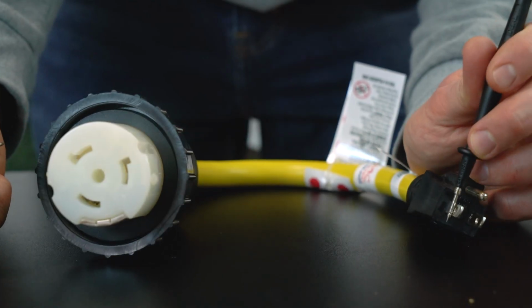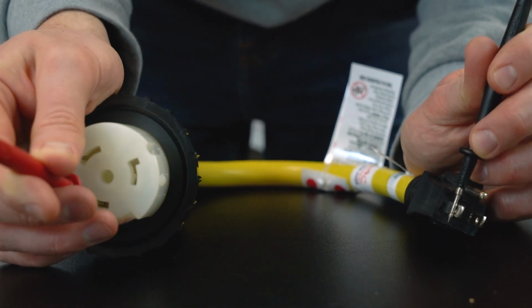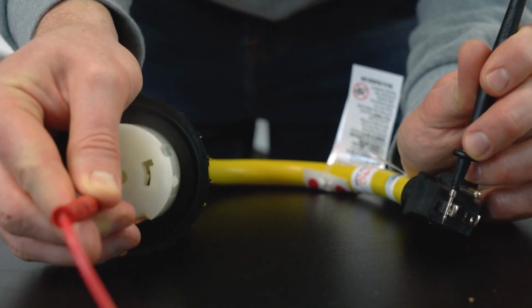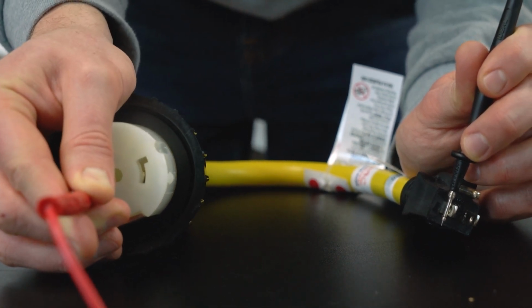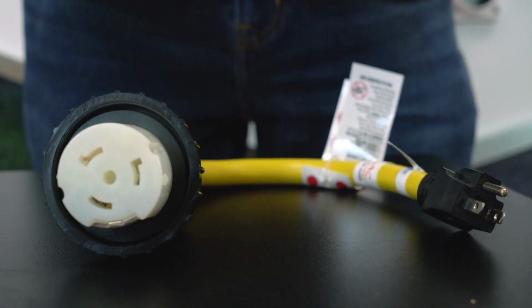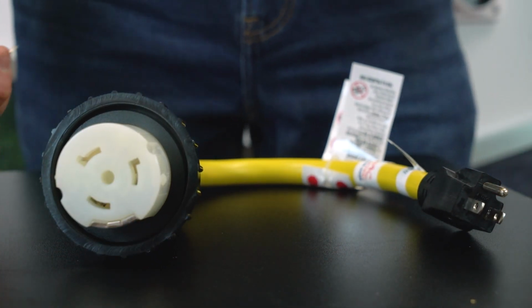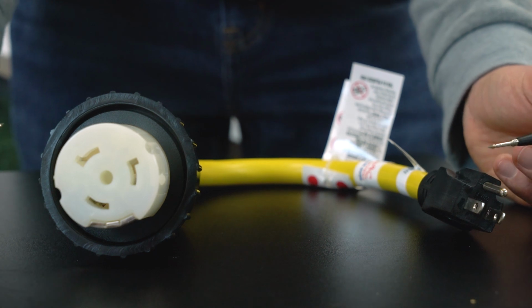Check continuity on the neutrals. Touch one probe to the neutral prong on the 5-15 plug and touch the other probe to the neutral slot on the SS250 connector. Again, you should see near zero resistance or hear the beep, which ensures proper continuity on the neutral path.